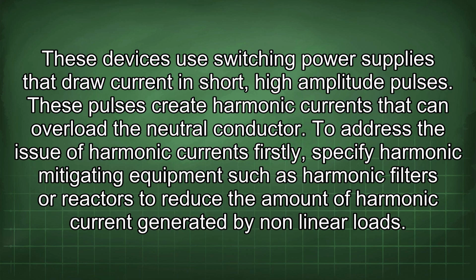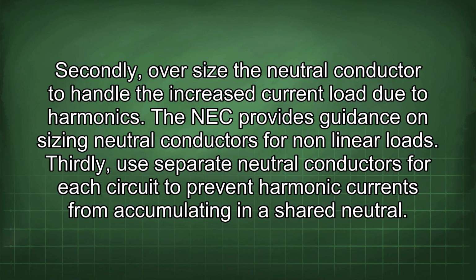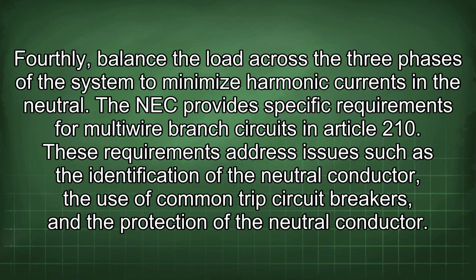To address the issue of harmonic currents, firstly, specify harmonic mitigating equipment such as harmonic filters or reactors to reduce the amount of harmonic current generated by nonlinear loads. Secondly, oversize the neutral conductor to handle the increased current load due to harmonics. The NEC provides guidance on sizing neutral conductors for nonlinear loads. Thirdly, use separate neutral conductors for each circuit to prevent harmonic currents from accumulating in a shared neutral. Fourthly, balance the load across the three phases of the system to minimize harmonic currents in the neutral.